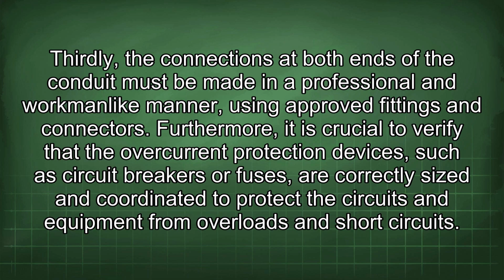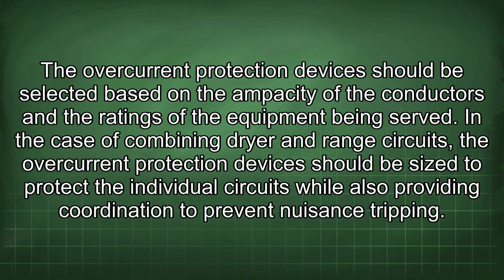Furthermore, it is crucial to verify that the overcurrent protection devices, such as circuit breakers or fuses, are correctly sized and coordinated to protect the circuits and equipment from overloads and short circuits. The overcurrent protection devices should be selected based on the ampacity of the conductors and the ratings of the equipment being served. In the case of combining dryer and range circuits, the overcurrent protection devices should be sized to protect the individual circuits while also providing coordination to prevent nuisance tripping.